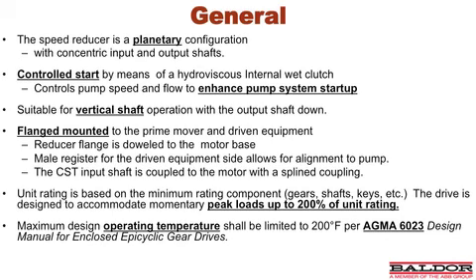So the specifications of our CST gear drive design, let's review the specifications specifically for a pumping application. In general, the technology specification for the CST gear motor in a pumping application entails a planetary configuration with concentric input and output shafts. The control start feature is incorporated by a hydroviscous internal wet clutch. This controls the pump speed and flow, thus enhancing the pump system startup. The technology is suitable for vertical shaft operation with the output shaft down. It's flange mounted to the prime mover and driven equipment. The reducer flange is doweled to the motor base. There's a male register for the driven equipment side. This allows for alignment to the pumps.